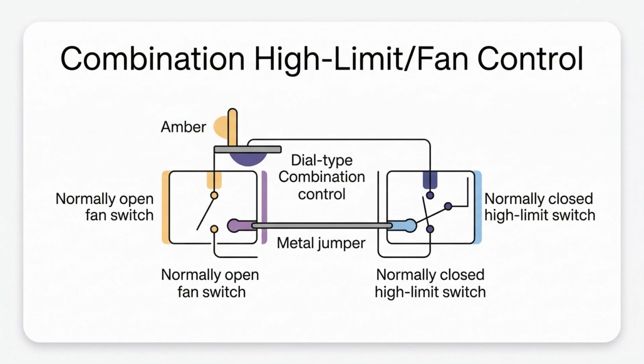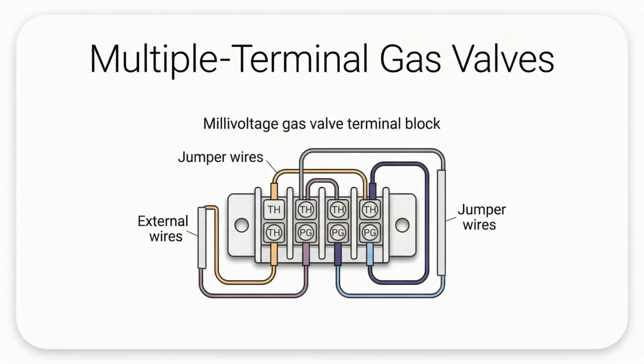Gas valves often look complicated because they have multiple terminals, but remember that the internal coil only needs two connections. The extra terminals and jumper wires are just there to act as a convenient connecting block for your thermostat, high-limit switches, and pilot generators. Finally, let's look at direct drive fan motors.